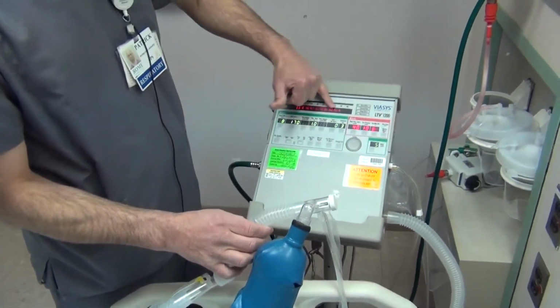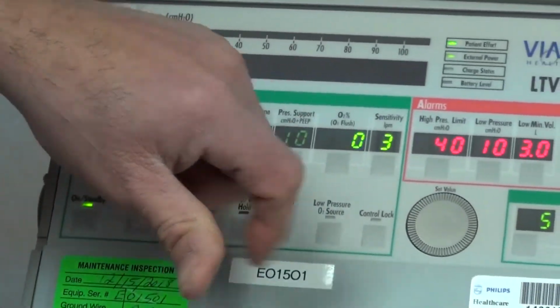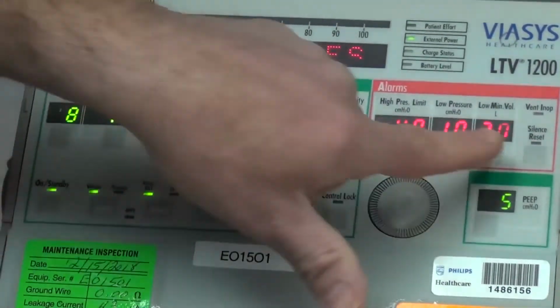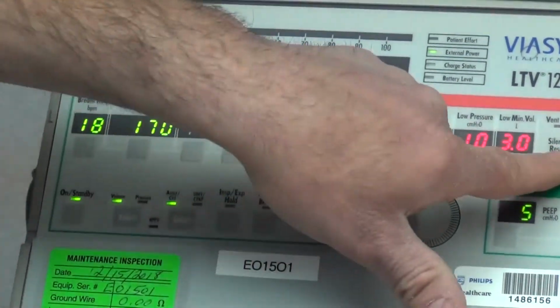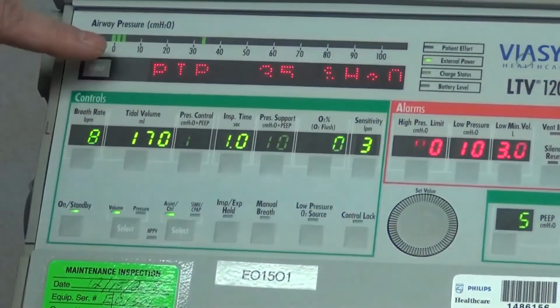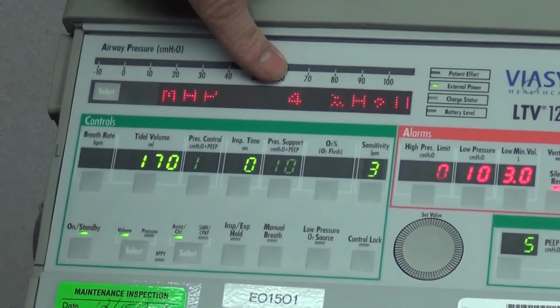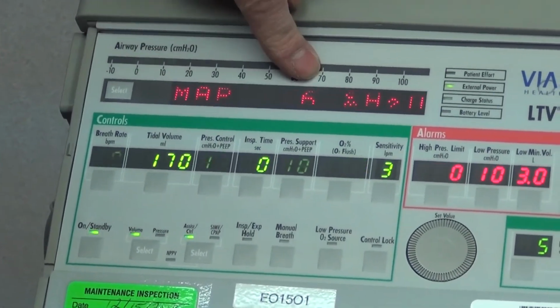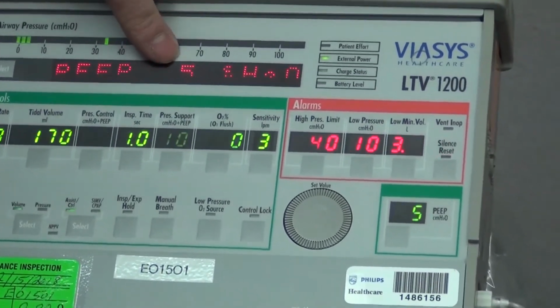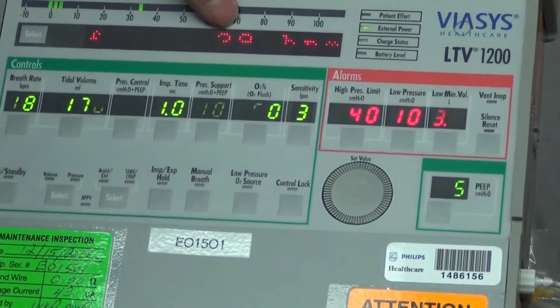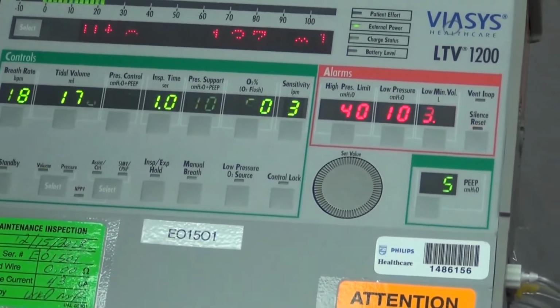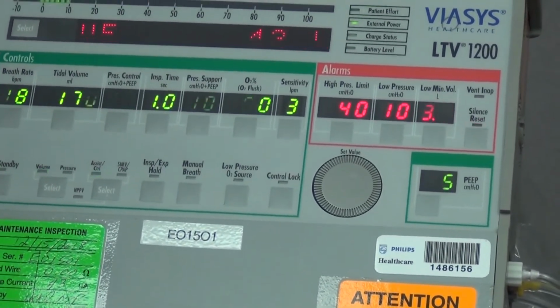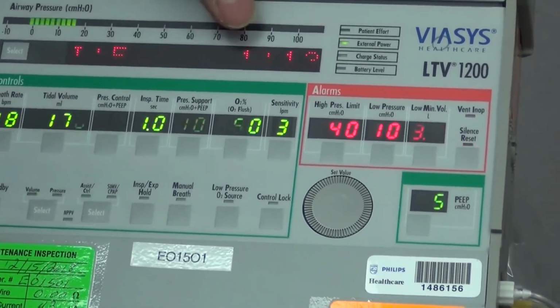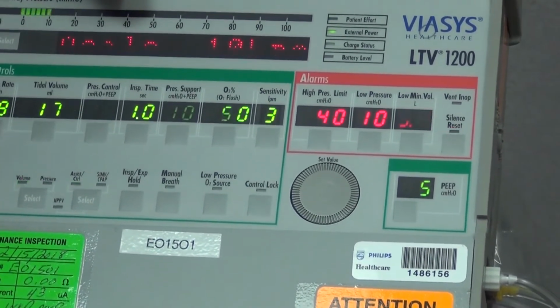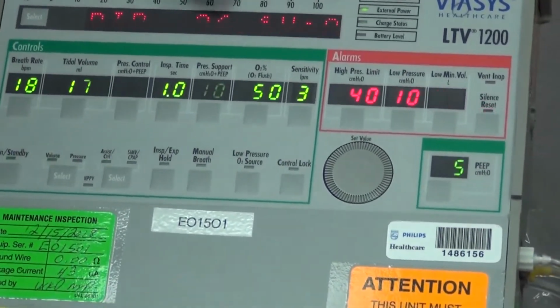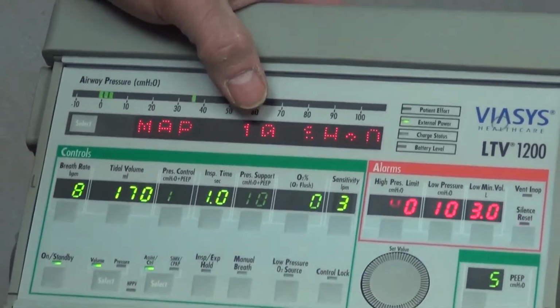Notice we still have an alarm at the top. It says disconnect sense. You just hit the reset and you can just go right through all of them. And when you're done, it'll just give your peak pressure, what it's currently set, or your mean airway pressure, and it cycles through all different things. Your PEEP is 5, your frequency is 29 breaths per minute, and it's being activated more than normal because I'm moving the tube a little bit. You got your IE ratio, and so anyway, it gives you an idea of what's going on. Like peak pressure is one of those important things to monitor.